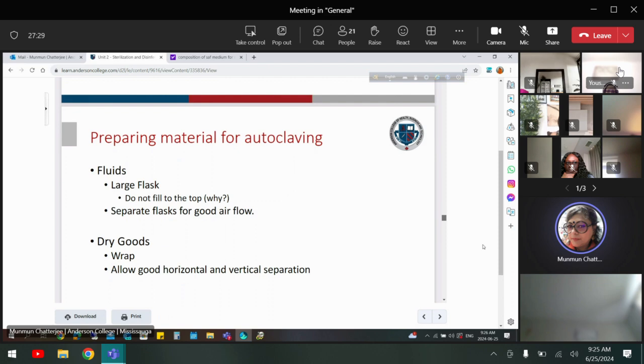Just to refresh, fluids should never be overfilled to the top because you first of all need good airflow, and also with the high temperature the liquid may overflow in the autoclave and the volume will be less. It's going to start boiling and then maybe overflow. So for large flasks, do not fill to the top. Separate flasks for good airflow, so separate each flask with a distance.